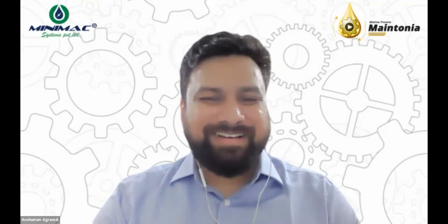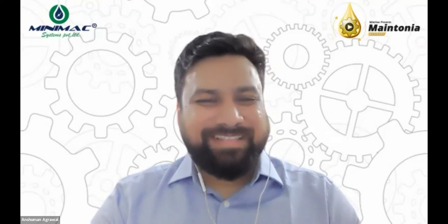But Mr. Anshuman, one more discipline is required. That is how we are removing the moisture. To maintain 100 ppm, if we simply boil the oil at 150 degrees to remove the moisture, that is not the method. By which method, and what is the maximum temperature we are going to achieve so that the oil will not get oxidized?